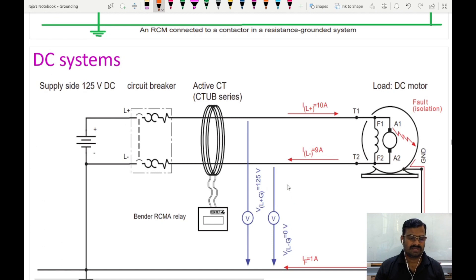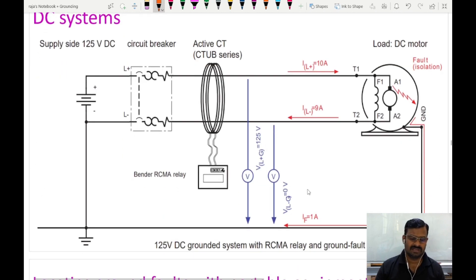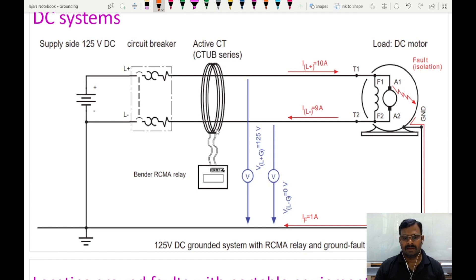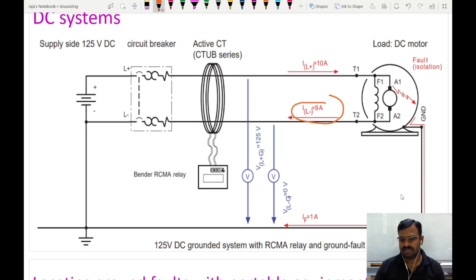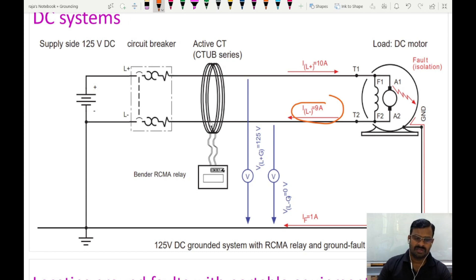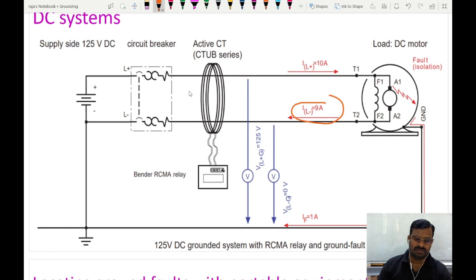In a DC system, solidly grounded devices are connected in much the same way. We use a CBCT and a relay to indicate the fault condition. Here we have 10 amperes of incoming current to the field and armature coil, but the return current is only 9 amperes because 1 ampere of fault current is flowing through the earth. The difference between incoming and outgoing current — 1 ampere — is detected by the CT, which gives a signal to the relay. The relay gives an indication or it can be connected to an MCB to open the circuit.